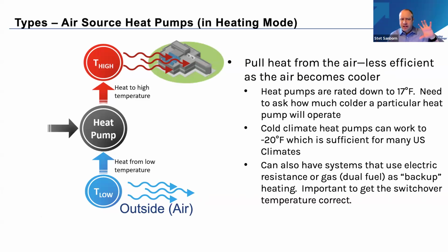Now, you've probably seen discussions of heat pumps and different types of heat pumps. I'm going to go through in a little bit some examples of that technology that you might see out in the marketplace. But in general, heat pumps are categorized by either air source or water source. In the case of air source, we're extracting heat from the outside ambient air and moving it into the building, in this case, in the heating mode. In summertime, we can actually extract the heat from inside the building and push it outside, even though it's very hot outside, using a reversible heat pump. But air source indicates what that source sink is. And it's typical, I'd say it's the most typical heat pump that we see, certainly in residential applications and light commercial as well. Next slide.